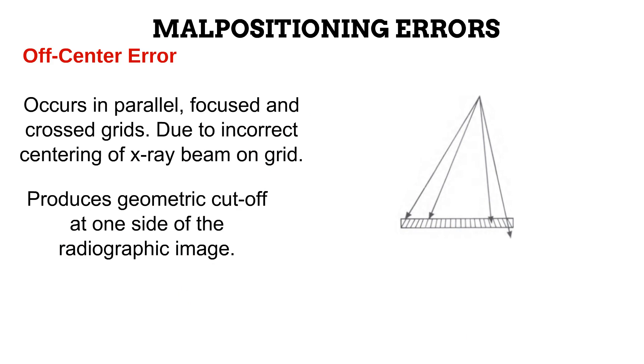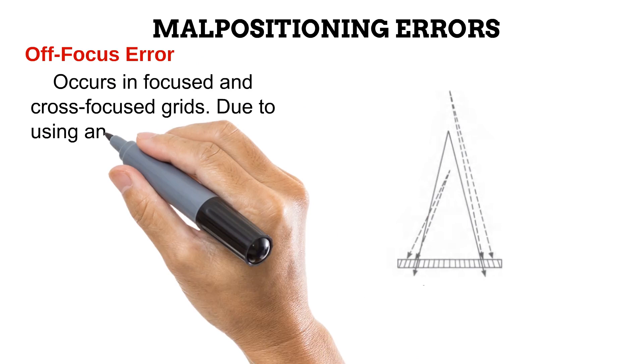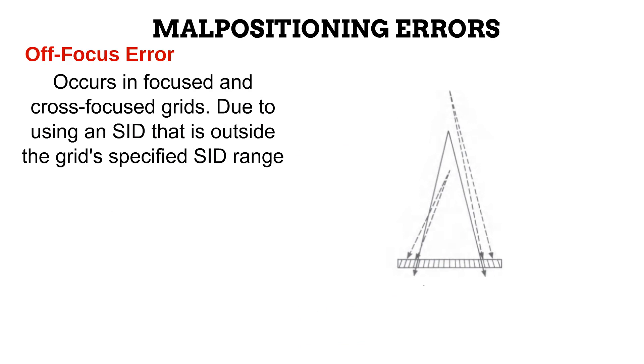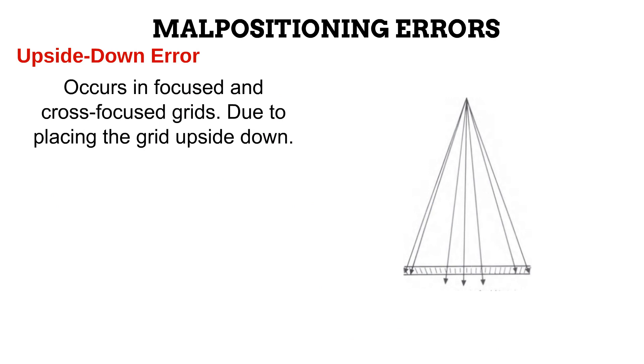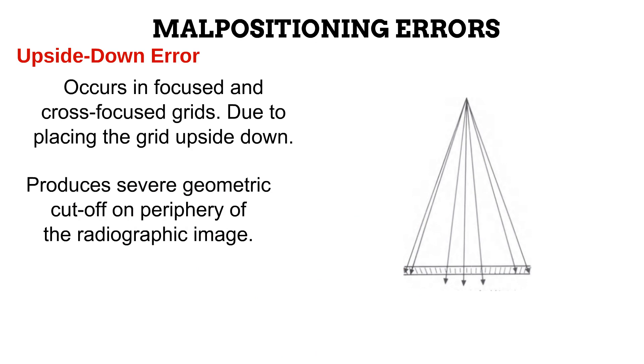Next is the off-focus error, which occurs in focused and cross-focused grids. Different focused grids are made for different source-image distances. If you use a focused grid at an SID it is not designed for, you get the off-focus error. For example, a focused grid labeled for use at 90 to 130 centimeters would produce an error if used below 90 cm or above 130 cm. An off-focus error appears as geometrical cutoff along the sides of the image. Lastly, the upside-down grid error occurs in focused and cross-focused grids, which have a front and a back. When placed upside down, severe geometrical cutoff is seen on the sides of the image.